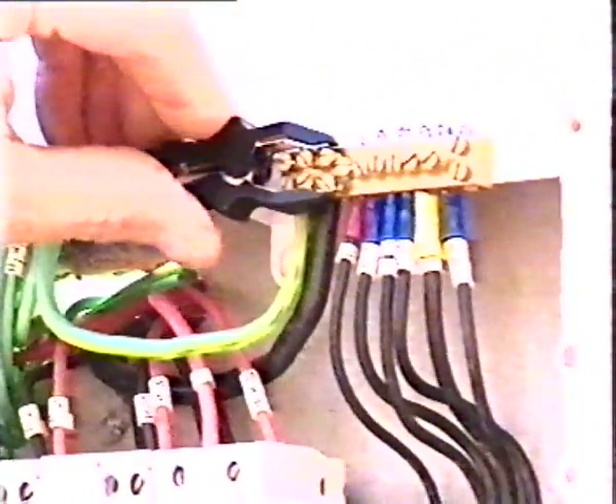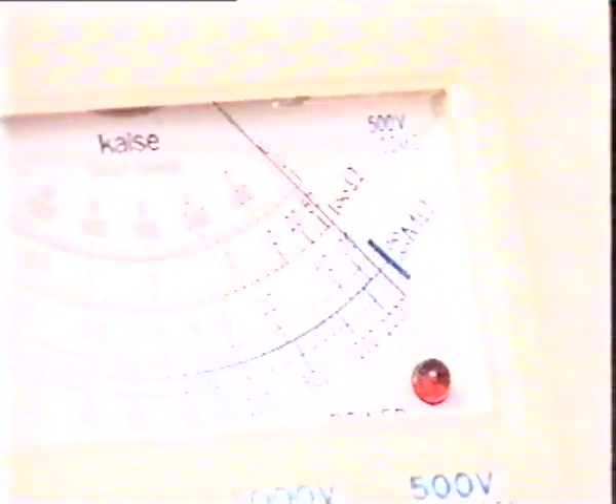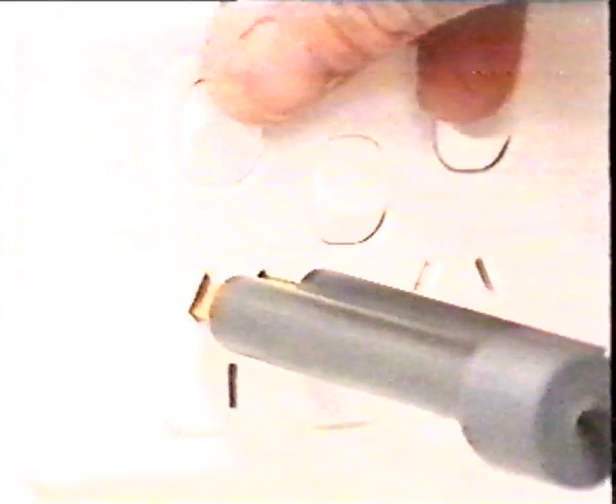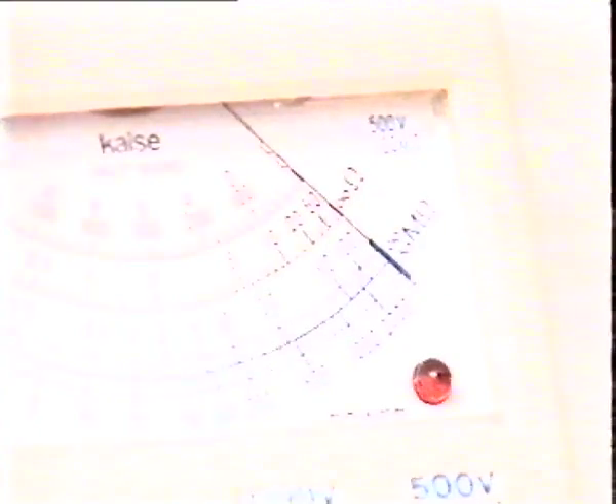To check the number of points per circuit, connect a 60-watt lamp or suitable resistor across each light and power circuit in turn at the switchboard. Using the ohm meter, test between active and neutral contacts at each socket outlet and unlamped lamp holder. Then record the number of points per circuit which are identified by the ohm meter indicating the lamp resistance.